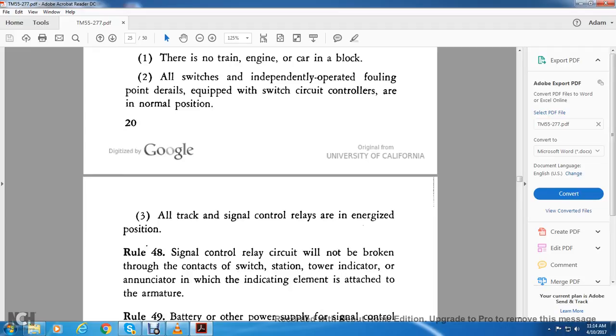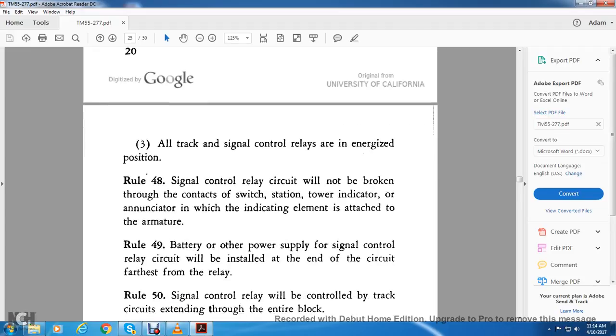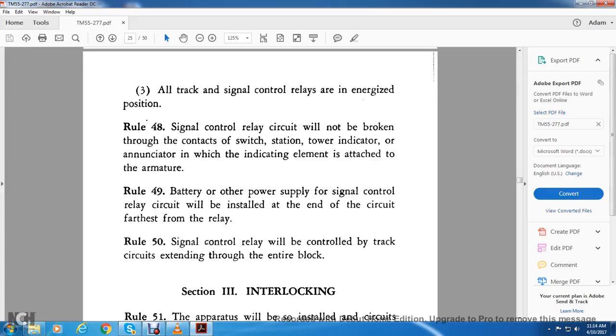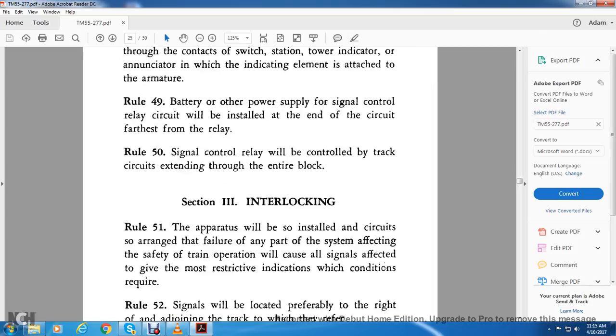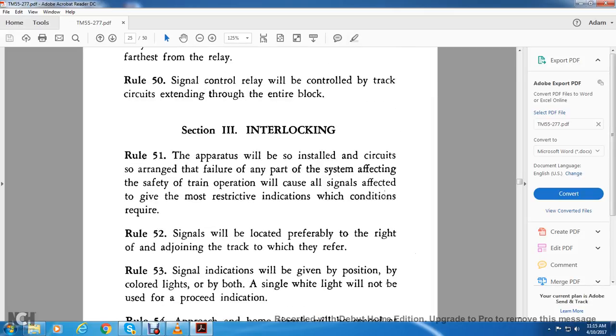Rule 48. Signal control relay circuits will not be broken through contacts of switch, station, tower, indicator, or annunciator in which the indication element is attached to the armature. Rule 49. Battery or other power supply for signal control relay circuits will be established at the end of the circuit farthest from the relay. Rule 50. Signal control relay will be controlled by track circuits extending through the entire block. Section 3. Interlocking.